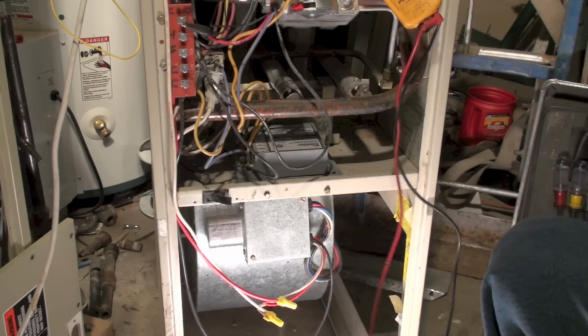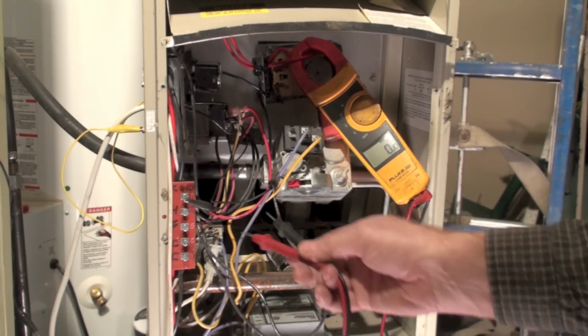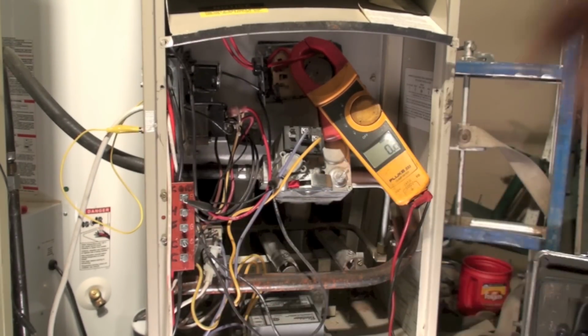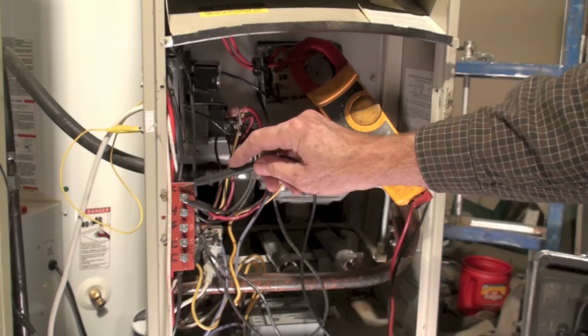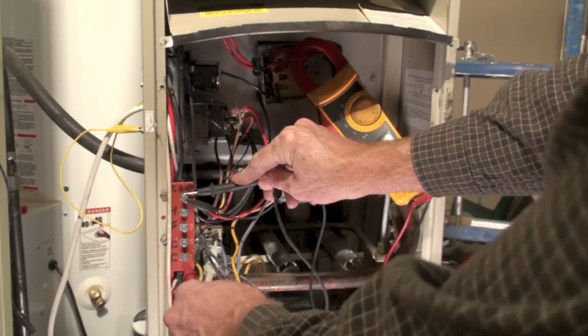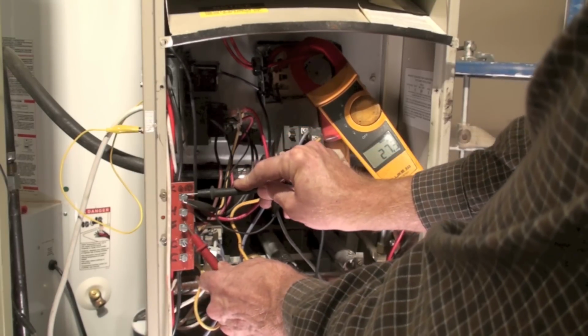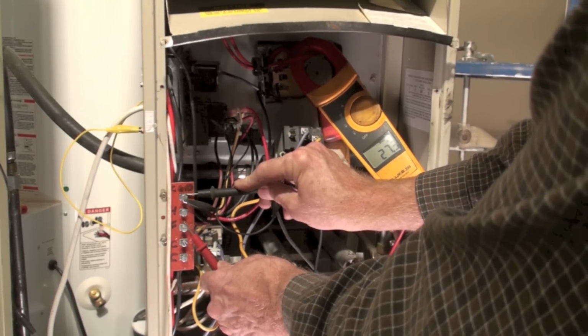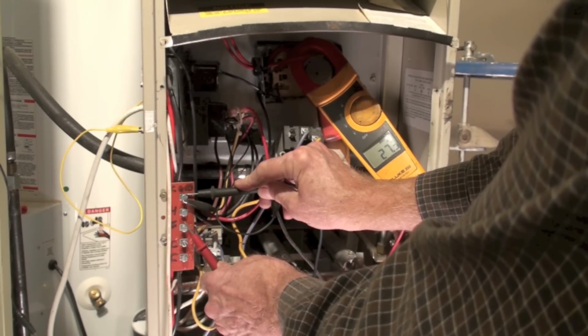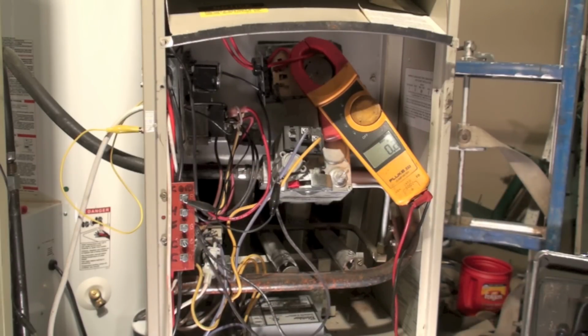So the first thing we're going to do, we've got our meter here, and we've got a pretty convenient terminal board here. Now, if I want to find out if there's voltage, this is the first thing you've got to find out. Is there voltage even to this silly thing? You can't go any farther unless there is. So let's go ahead. R is one of the terminals for low voltage, and C is the other. If you show voltage here, then you can continue on. If you do not see voltage here, then you're going to have to find out if you have 120 volt power. There should be a light switch type switch nearby the appliance. Make sure that's on, make sure your breaker's on, and then double check here.